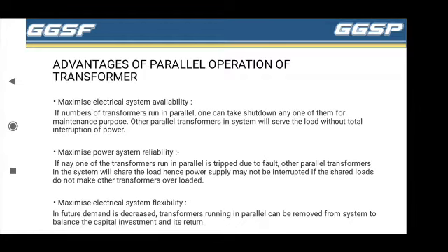Advantages of parallel operation of transformers. First advantage, it maximizes electrical system availability. If a number of transformers run in parallel, one can shut down any one of them for maintenance purposes. The other parallel transformers in the system will serve the load without total interruption of power.